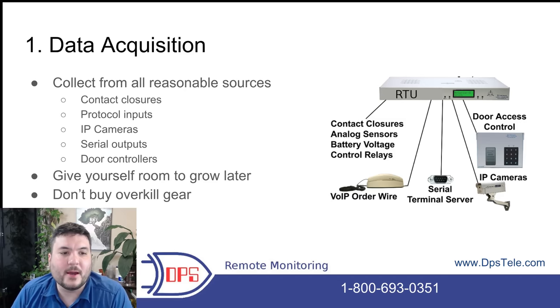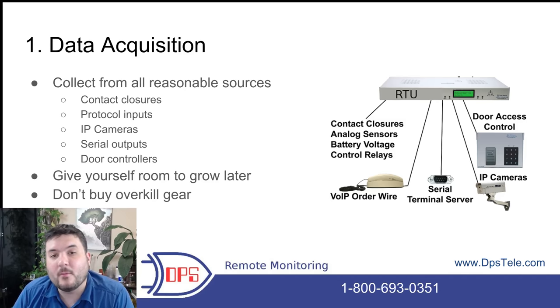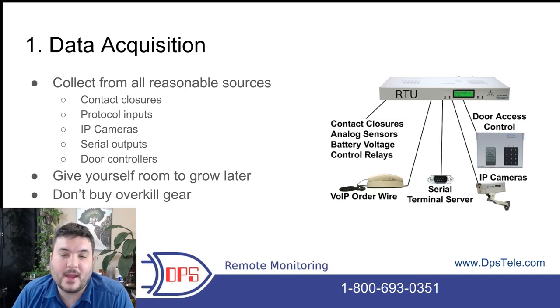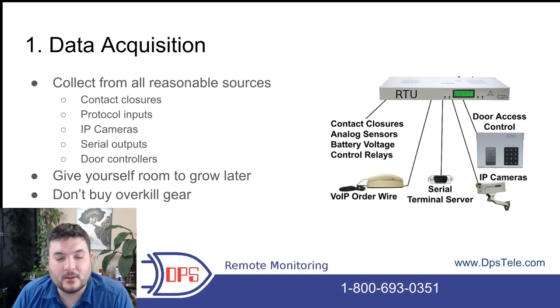Getting deeper into data acquisition — you want to collect information from all reasonable sources, but don't go overboard. Contact closures are common: if you have a piece of gear that latches a relay to tell you it's running, overheating, or has a high noise level, most equipment manufacturers will give you at least a few relays to signal a problem. If your RTU has discrete inputs, you can wire those in and monitor them. Protocol inputs are similar but based on a communications protocol instead of a physical contact closure — the device sends a message, your RTU picks it up and processes it, and some messages can go straight to the master.